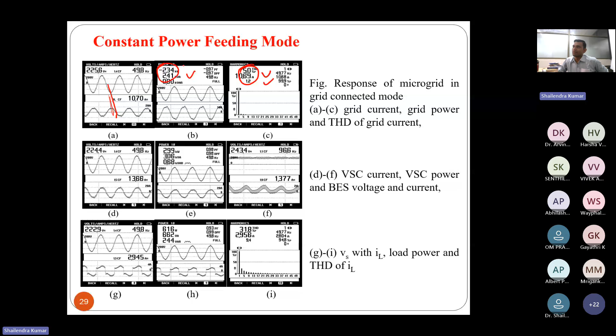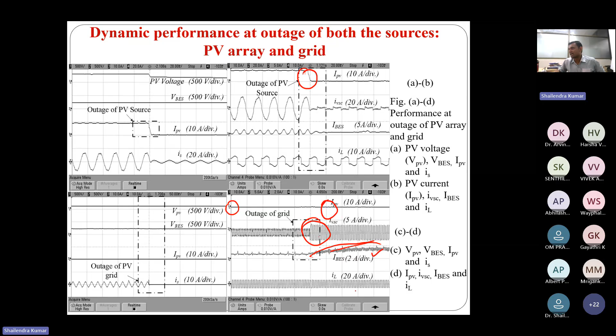And these are scenarios under outage of both sources - grid outage is there, and PV source outage is there as well. If both sources are out, you can see the battery discharge rate is increased because now the battery is feeding power to the load. So VSC current is also increased because power is coming from the battery. However, PV current is 0 here - you can see PV is at 0. So PV current is 0, but the battery is discharged to feed the load here.